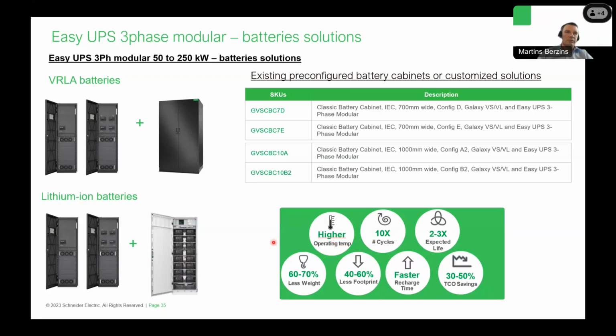Charge and discharge cycles for lithium-ion are 10 times more than for lead-acid batteries. We have an expected 2 to 3 times increase in life for the lithium-ion solution, which is 10-15 years plus. For example, with lead-acid batteries, the design life is 8 to 10 years, but in reality, depending on the site and usage, the battery change typically already happens at the 5th or 6th year. With lithium-ion, 15 years is the expected lifetime. Lithium-ion has less weight and less footprint. For example, if we take these two cabinets, and take a 50 kilowatt UPS model and equip it with this one lithium-ion battery cabinet, that would give us a 30-minute runtime at 50 kilowatt load.